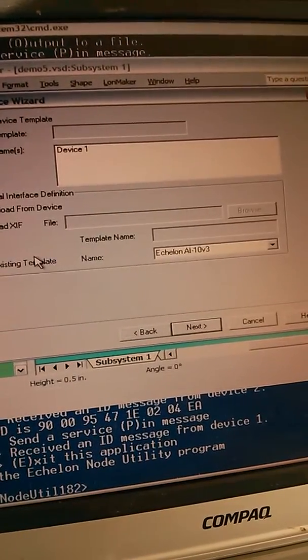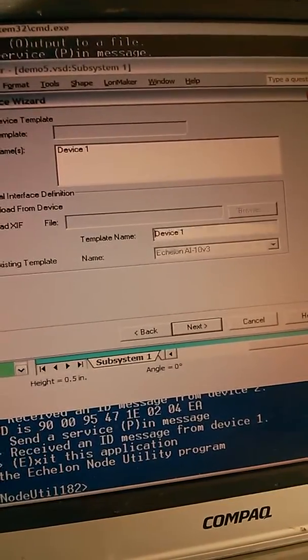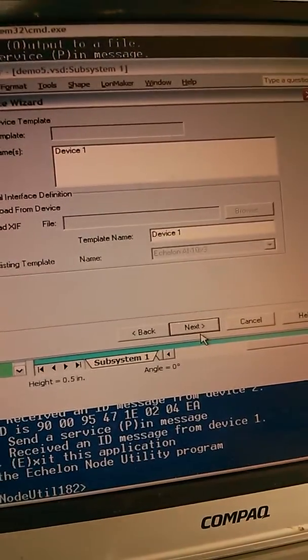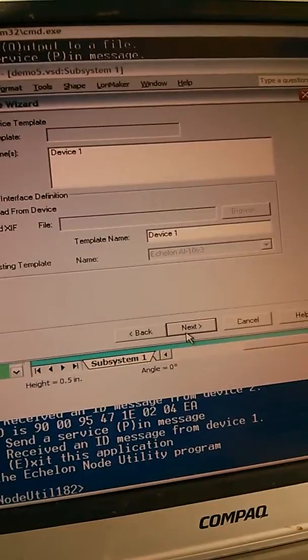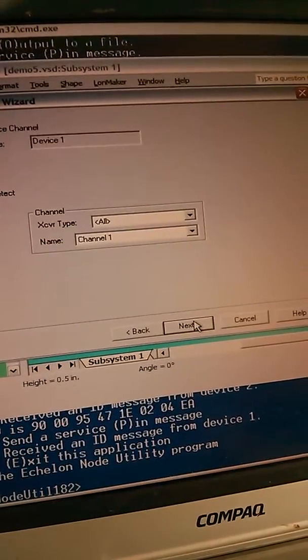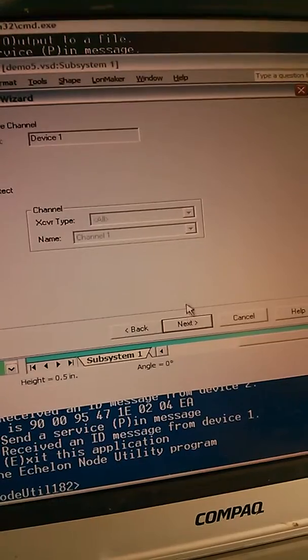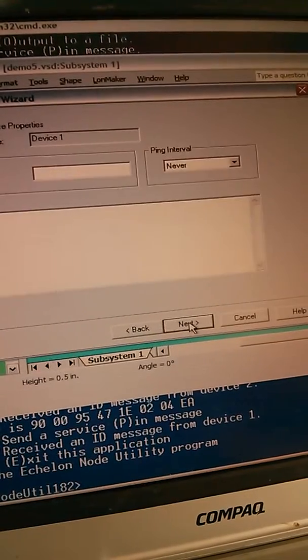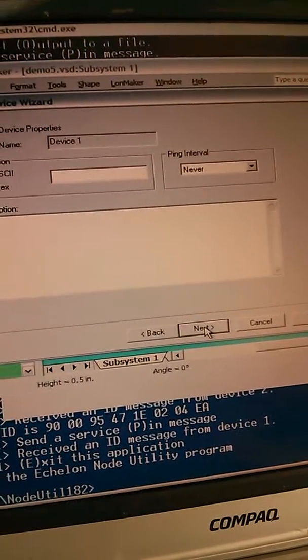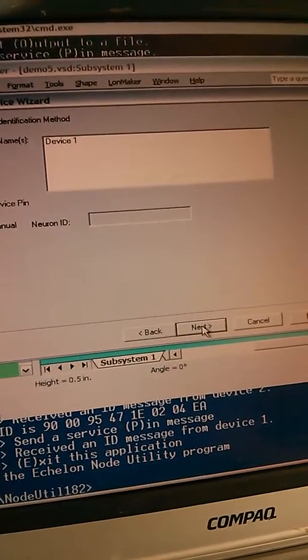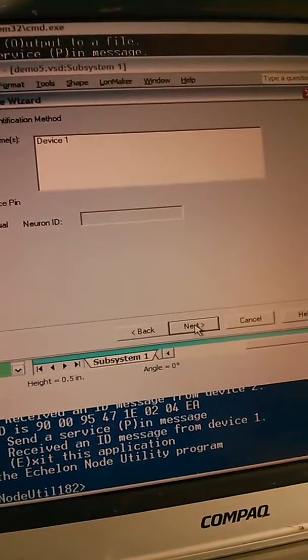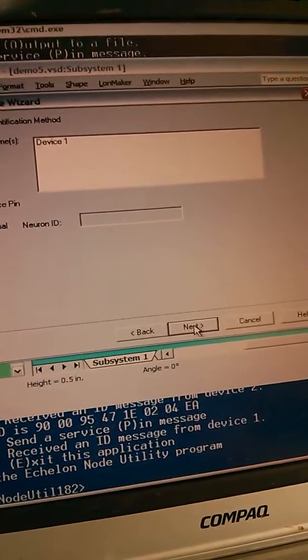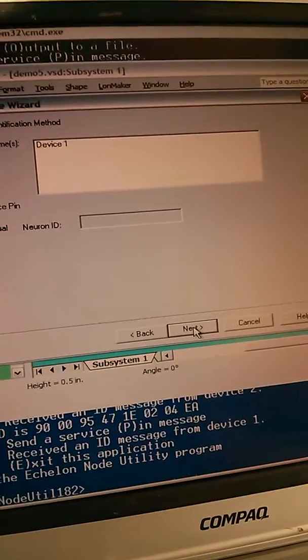I'm going to upload the XIF from the device itself. If I had the XIF, I could load it here by browsing to it. Set that to auto-detect. And I'm going to commission using the service pin. You could also commission by typing in the Neuron ID if you knew it.